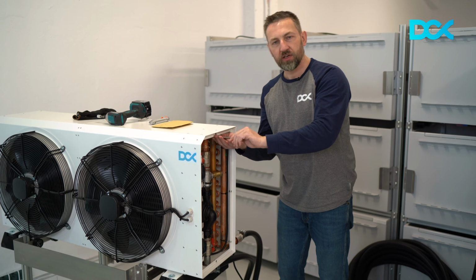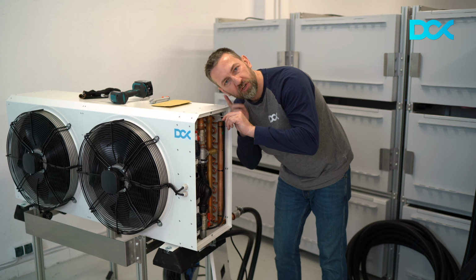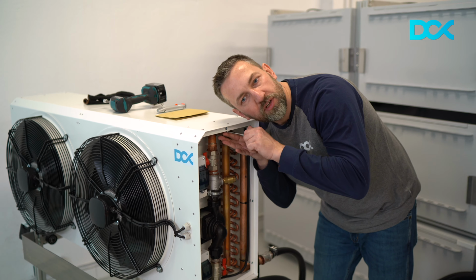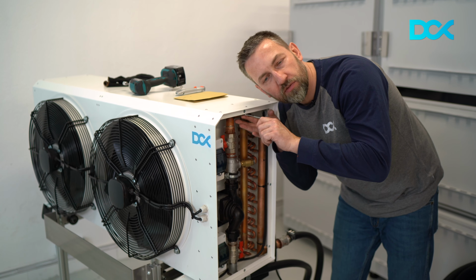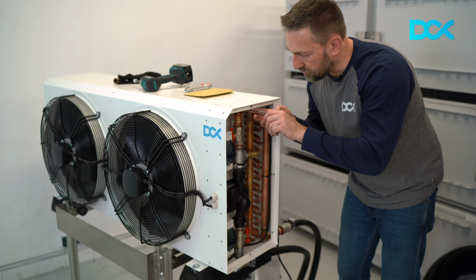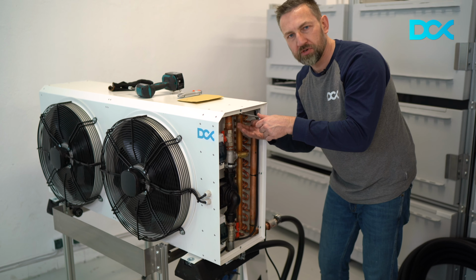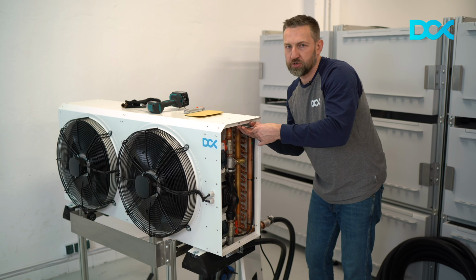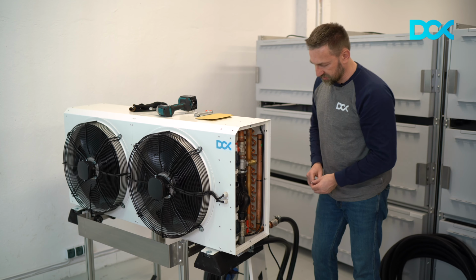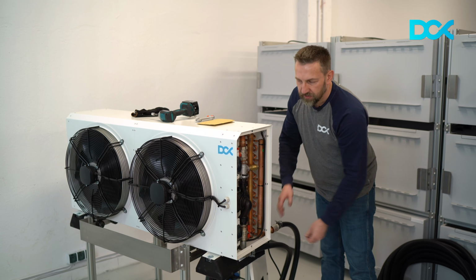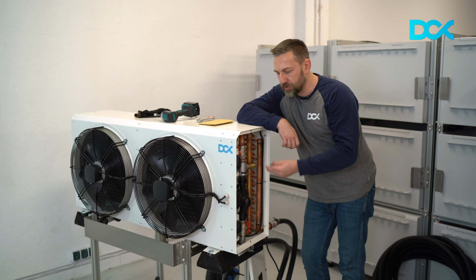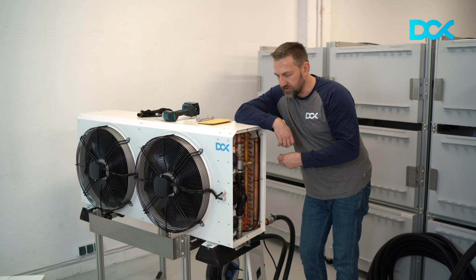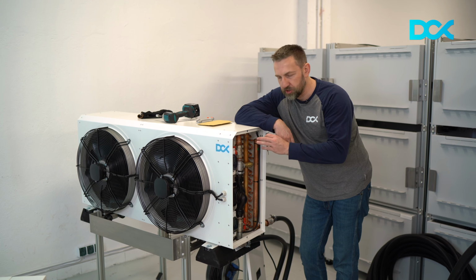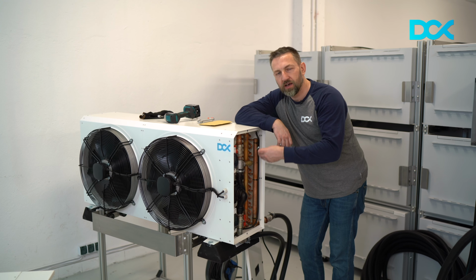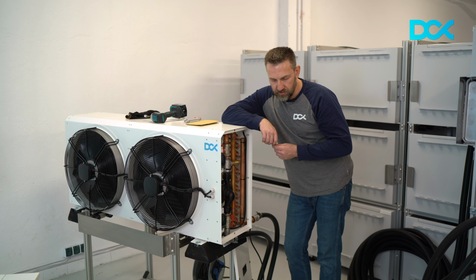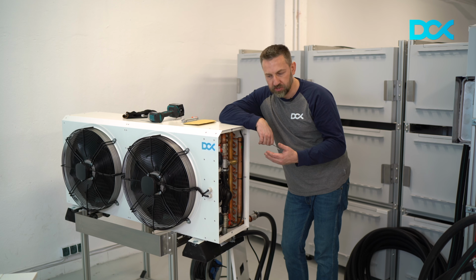And you just unscrew it, and you listen whether you hear any air being released from the system. You should hear just a little bit of air going out. You can hear the sucking sound, and after that, when you see that the water is dripping here, then you close the valve. So this is the usual venting as with any other hydraulic system, and the same procedure on that side. It may happen that after some time of operation, especially when you have heated up the system and hot water is going through it, you will need to perform that procedure again and again, and control the unit after some time to see what's happening, maybe adding some pressure.